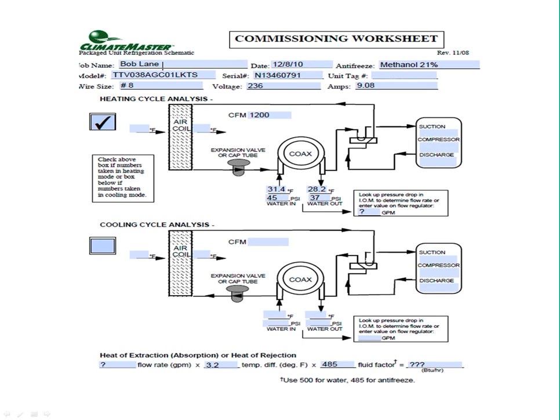See if that makes it fall in line so you can at least do your test. Now, in all fairness, some folks may put 2 pumps on there because perhaps, in this case, we know it's methanol, but if the installer was using the propylene glycol, remember, they have to get upwards of 4 GPM per ton to try and get turbulence out in the loop field. So that could be why they have the 2 pumps, so that they can deliver that kind of flow rate, but it doesn't help you for your test.